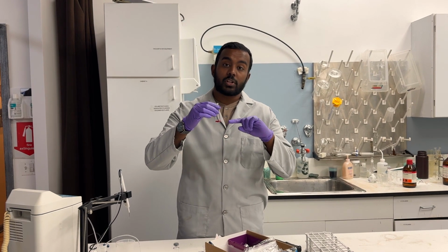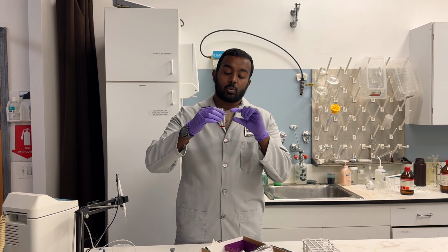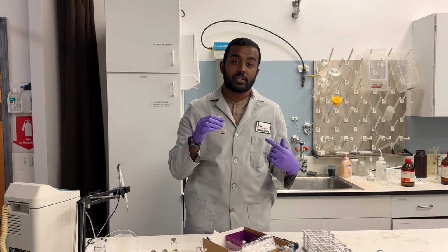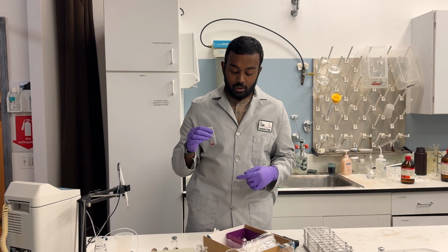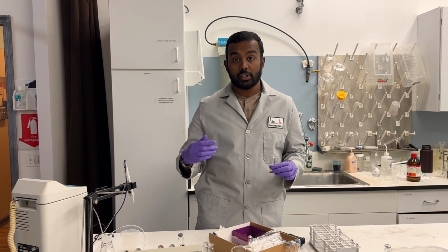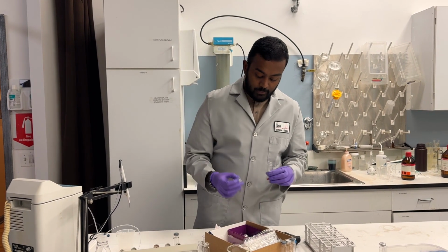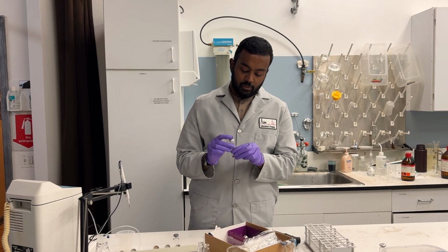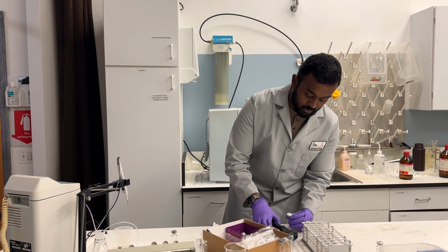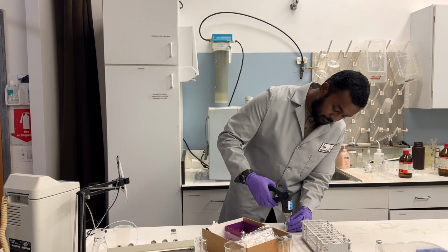So there's a certain percentage of ethanol in the blood. We're going to measure the vapor above the sample, and that's going to tell us exactly how much ethanol was in the blood, specifically how much the defendant or our client in this case consumed. So after that point we have to make sure that it's vacuum sealed. So I'm going to go right here, just a crimper.